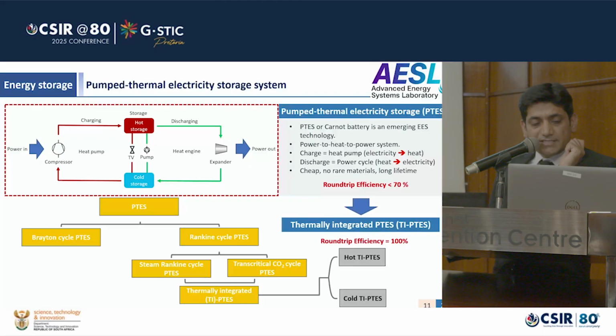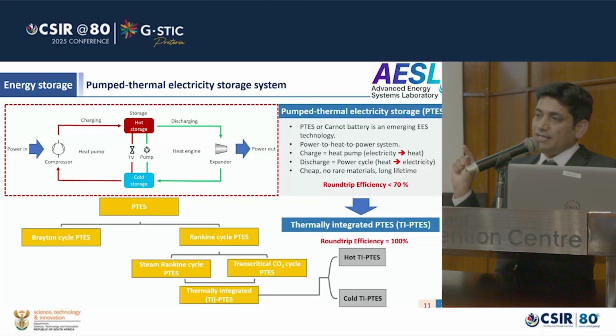Conventionally, the round trip efficiency of pumped thermal electricity storage system is less than 70%. However, Rankine cycle has the unique characteristic that it can integrate a low temperature external heat source during the charging or discharging cycle, which can boost its round trip efficiency to equal 100% or even above.